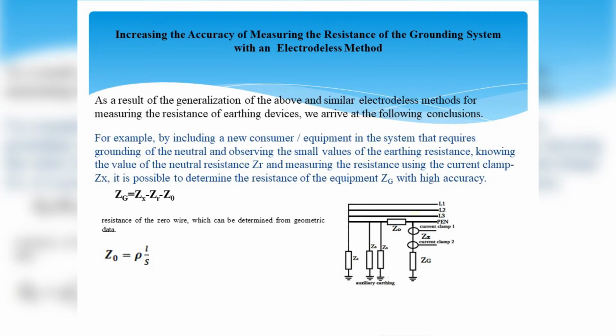As a result of the generalization of the above and similar electrodeless methods for measuring the resistance of earthing devices, we arrive at the following conclusions. For example, by including a new consumer equipment in the system that requires grounding of the neutral and observing small values of the earthing resistance in the figure, knowing the value of the neutral resistance ZR and measuring the resistance using the current clamp ZX, it is possible to determine the resistance of the equipment ZG with high accuracy.